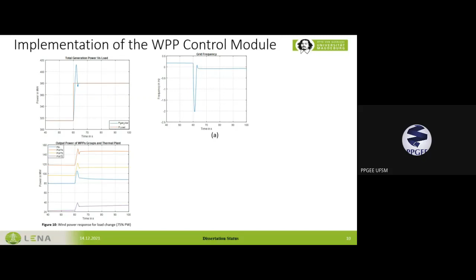If we make it 100% wind, the frequency change increases more than before. Depending on the grid codes, if this is allowed, we can operate with 100% wind turbines, but the change increases to more than 2 hertz.